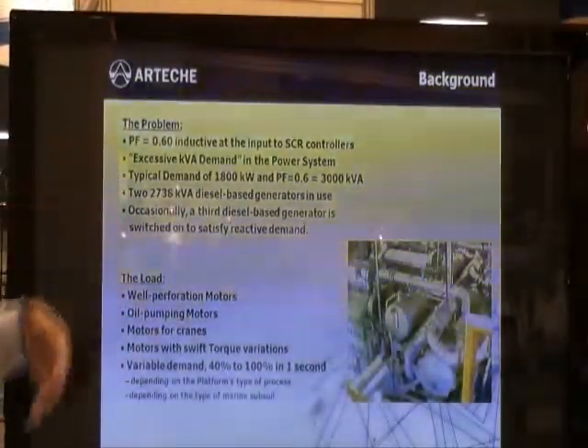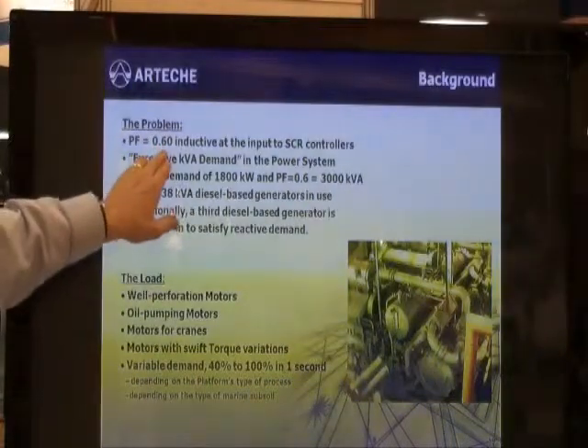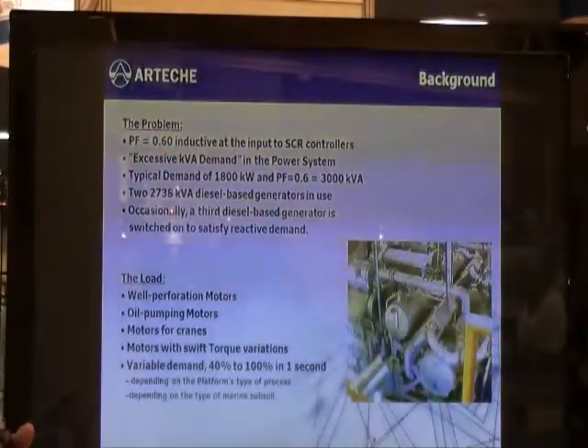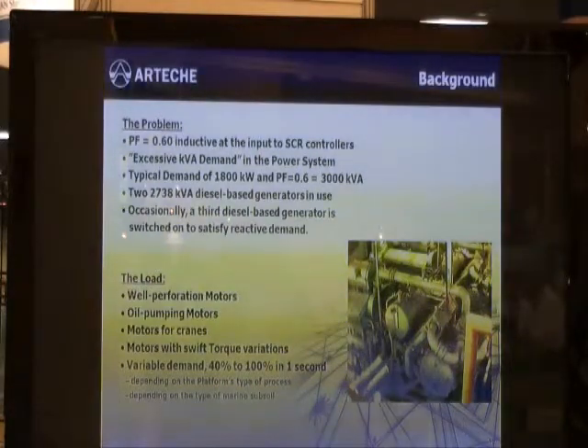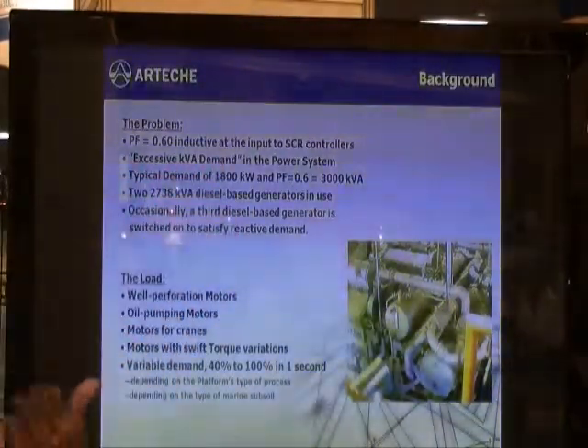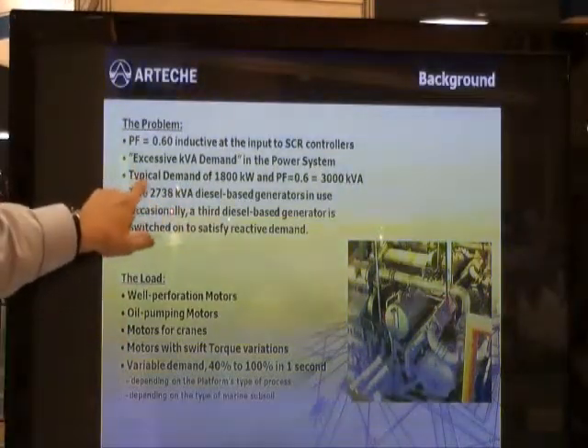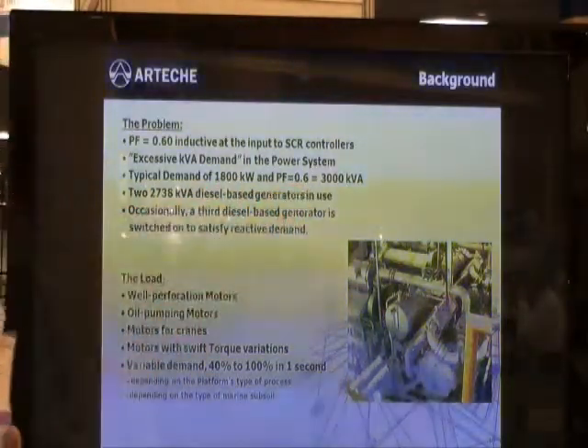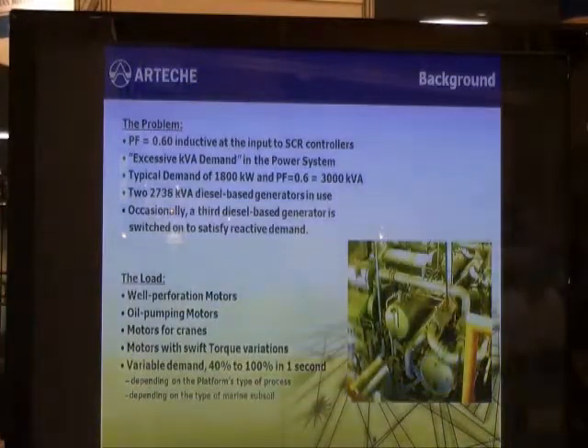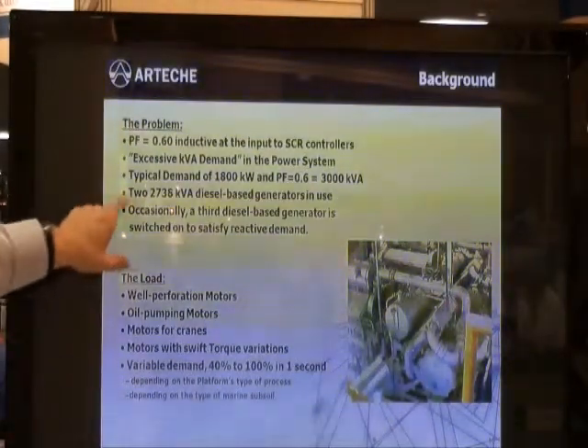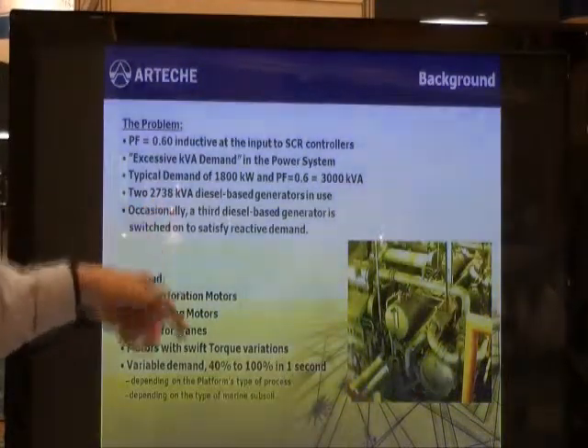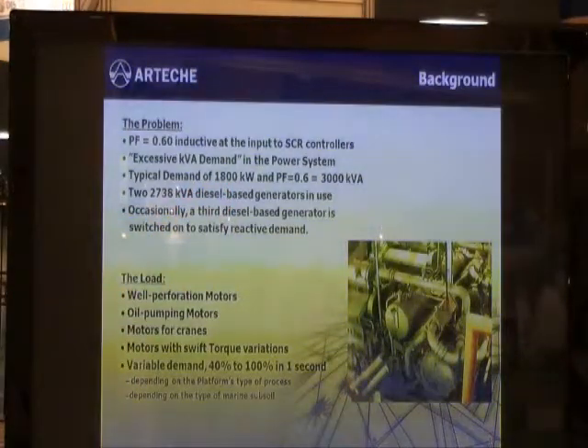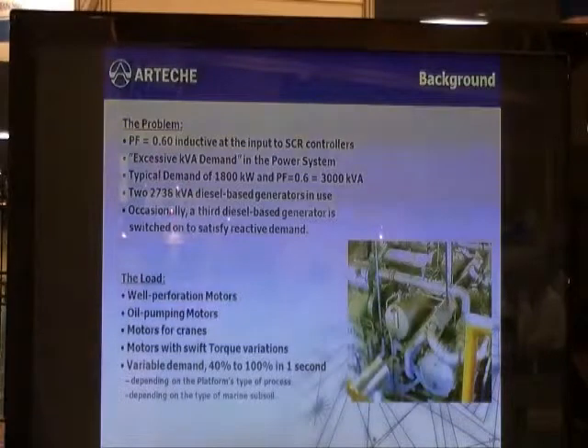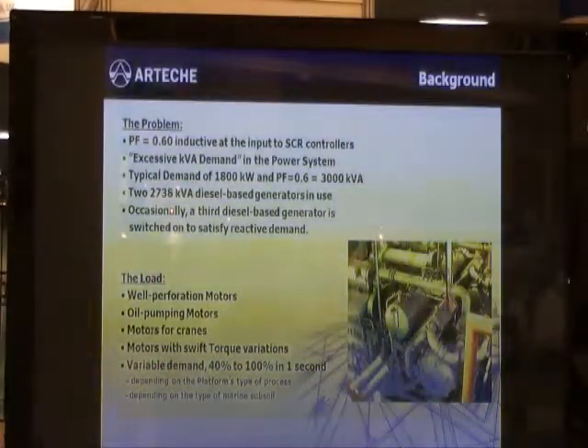The problem here is that the power factor on this system was 0.6 inductive at the input side of those SCR controllers or DC motor drives. There was an excessive kVA demand based on the generation capability. The typical demand of 1,800 kilowatts with a power factor of 0.6 required 3,000 kVA or 3 MVA of generation. So two 2.7 MVA generators were required to supply this load, even though it was only 1,800 kilowatts. And on occasion, a third diesel-based generator had to be started to fully operate those loads.